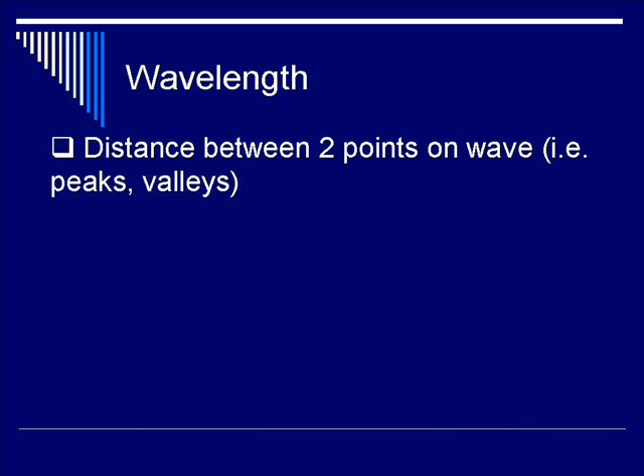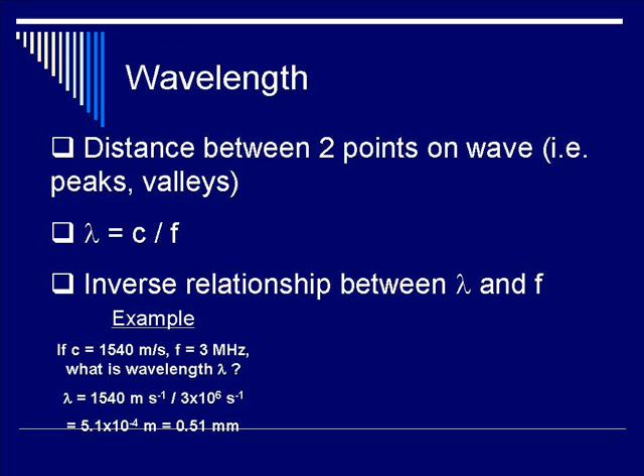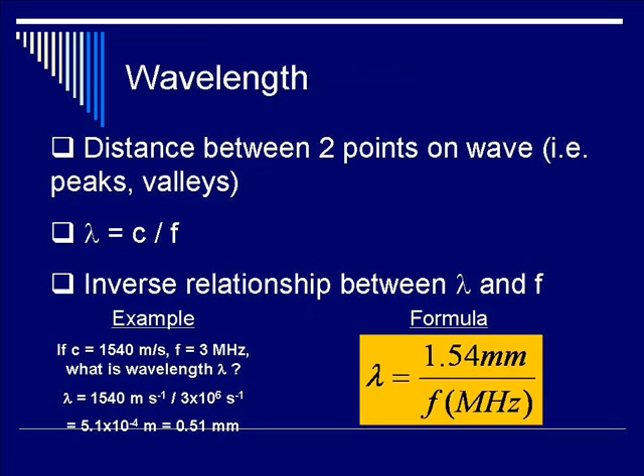Wavelength is defined as the distance between two points in a wave — for example, the distance between two peaks or two valleys of a sound wave. The equation is lambda equals c divided by f, where c is the speed of sound in the medium and f is the frequency. There is an inverse relationship between lambda and f. For example, if c is 1,540 meters per second and f is 3 MHz, then lambda equals 1,540 divided by 3 times 10 to the 6 Hz, which equals 0.51 millimeters. A better equation to remember is lambda equals 1.54 millimeters divided by f expressed in megahertz.